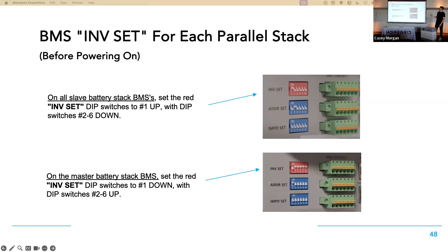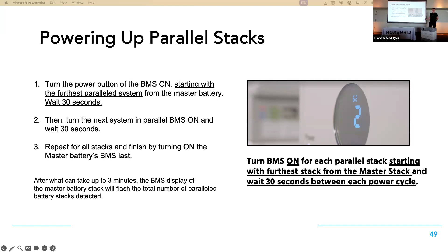We can power up the parallel stacks. The way you do this — and again, you're not going to remember this, but just in case — you're going to turn the power button of the BMS on, starting with the furthest paralleled system. Let's say this was the master BMS; you head all the way down to the last one, turn that one on, wait 30 seconds, then go to the next one, turn it on, wait 30 seconds, go to the next one, turn it on, wait 30 seconds, and then head to the last one. After about what can take up to 3 minutes, the BMS on the master battery is going to flash the number that's in parallel. So if you had 8 systems, it's going to flash 8 — it's basically in detection mode, but this time for batteries in parallel.